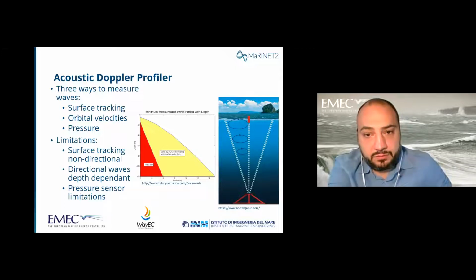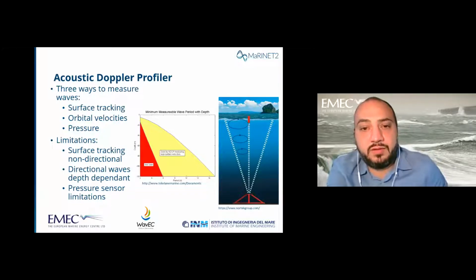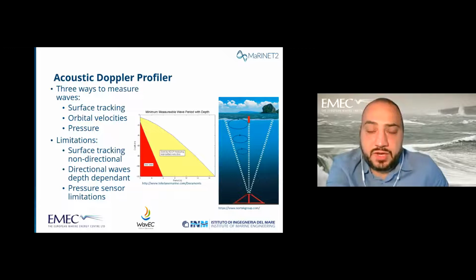One is based on pressure, because most of them, if not all, come with quite accurate pressure sensors, but that comes with the limitations that I mentioned earlier. The other way is using surface tracking, because you can detect the surface really well from the acoustic signal. There's a spike in the strength of the reflection.